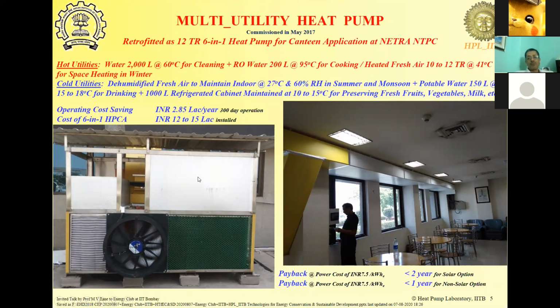Now the beauty is, although the heat pump operates for only 6 to 7 hours a day, that is a couple of hours in the morning during breakfast time, 3 hours during lunch time, and 1.5 hours in the evening, the hot water, chilled water, as well as the cooking water, RO water, is available 24/7. In fact, the chilled water from this unit is available for gardeners and watchmen even during the weekends when the facility is actually not operated during the day. So this has pretty good paybacks also, payback of less than 2 years, even if solar water heaters are already installed. And in situations where the solar water heaters are not yet installed, we can offset the cost of the solar water heater through the cost of this unit, and then the payback becomes even less than that, even just 1 year payback is possible.